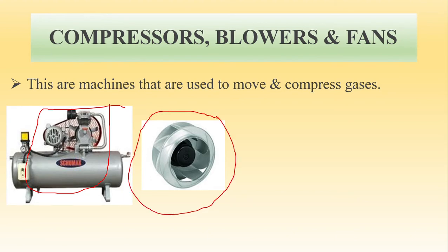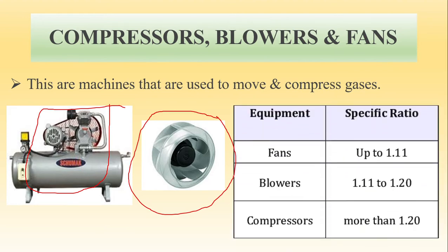This particular photo is nothing but a small fan. The question arises: what is the difference between a compressor, blower and fan? All three devices are used to move or compress gas. Technically, a device is called a fan if it increases pressure up to 1.11 times the input pressure. If the ratio is approximately 1.11 to 1.2, we call it a blower. Above 1.2, the compression ratio makes it a compressor. All three devices work on a similar principle — pressure at output is higher than pressure at input, and that is how there is a flow of fluid.